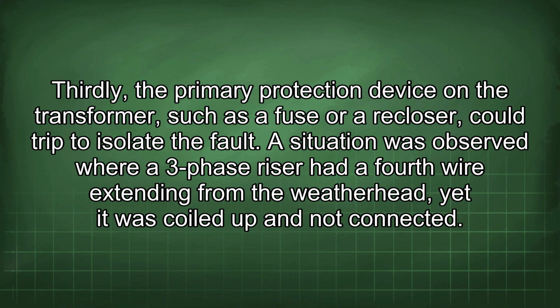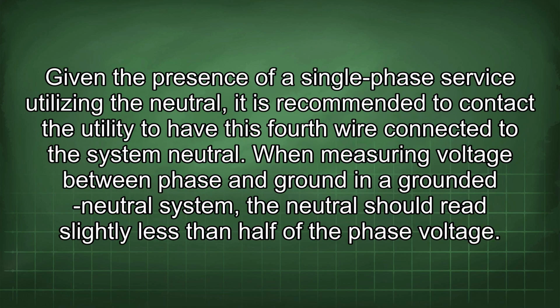fault. A situation was observed where a three-phase riser had a fourth wire extending from the weatherhead, yet it was coiled up and not connected. Given the presence of a single-phase service utilizing the neutral, it is recommended to contact the utility to have this fourth wire connected to the system neutral.